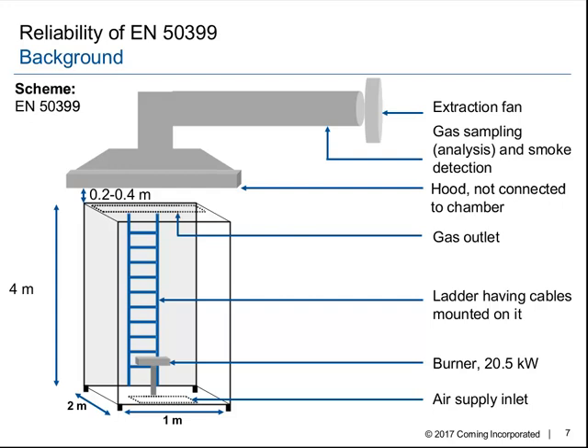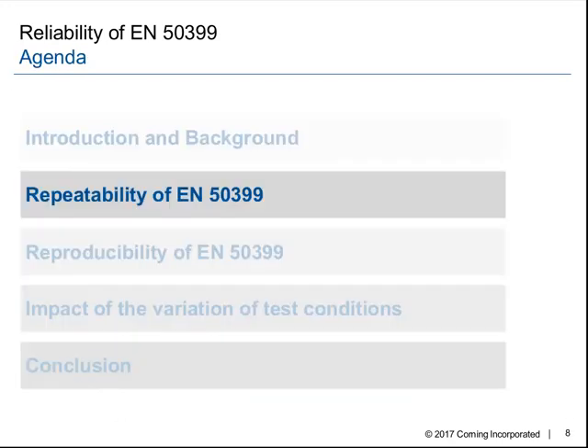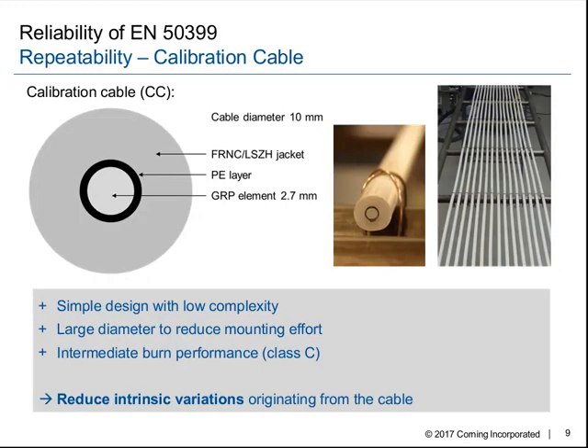Since we were looking on real cables tested in it and the results slightly varied, we thought it's a good idea to look on the repeatability with a kind of calibration cable. So we invented this calibration cable, which is shown here. This calibration cable has a very simple design with low complexity. It has a GRP in the middle, followed by a polyethylene layer, so a material which combusts very fast with a rather high peak of the heat release, followed by an FRNC material, so material which is combusting slowly with a rather low heat release or peak in the heat release. And due to this mixture of these different materials, we wanted to achieve an intermediate burn performance.